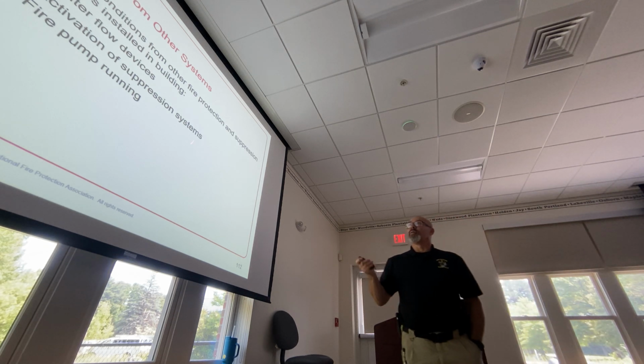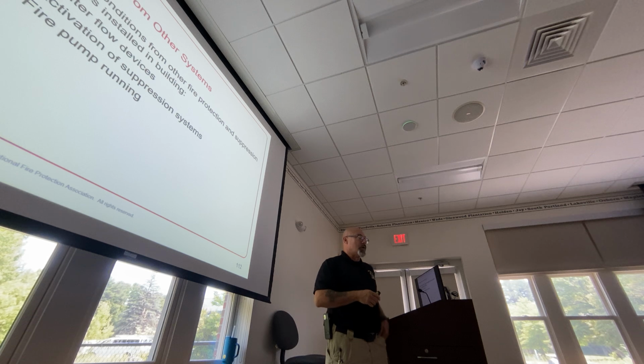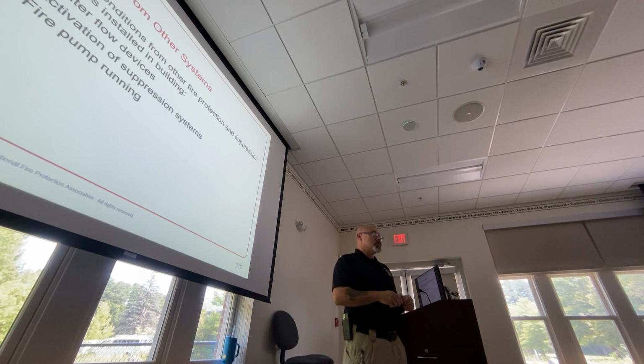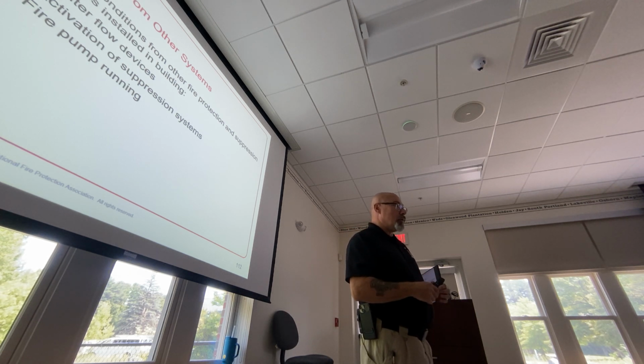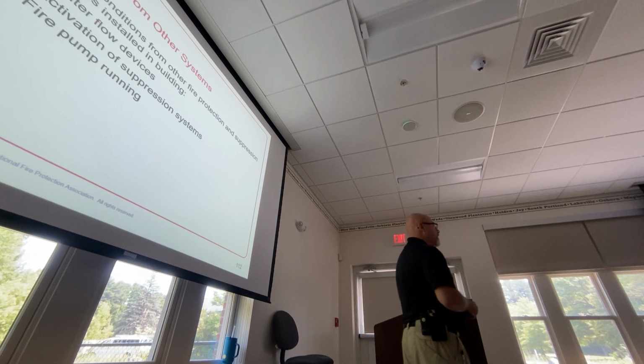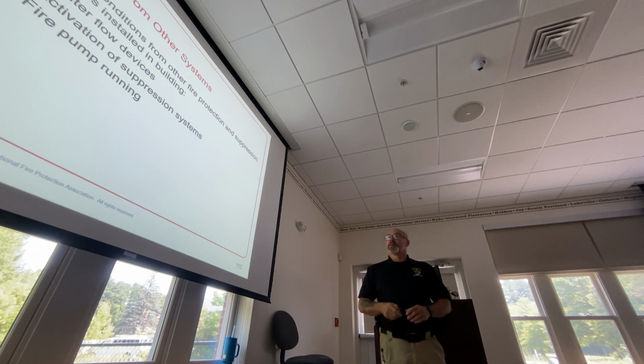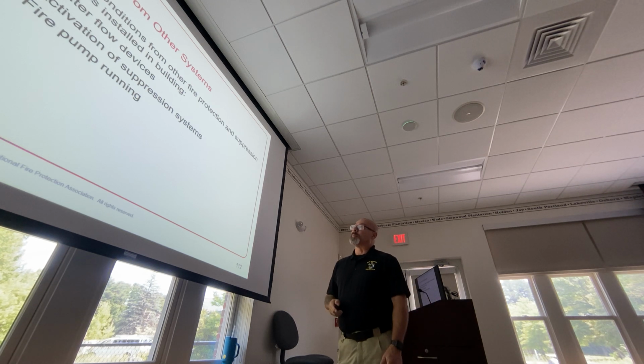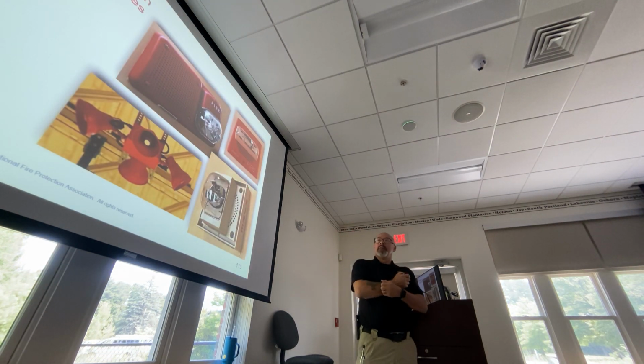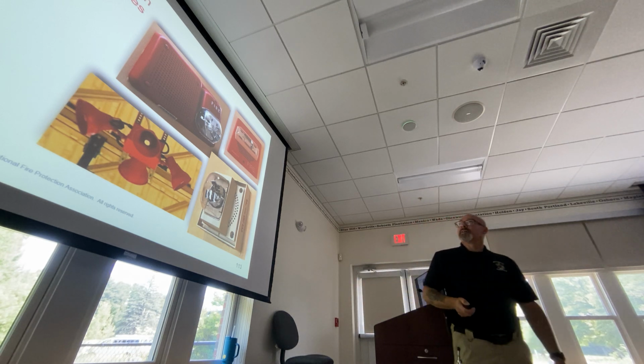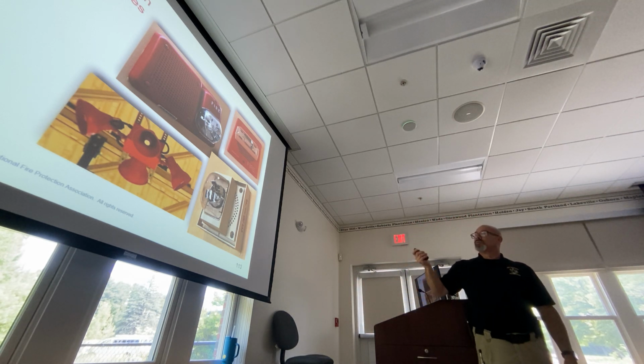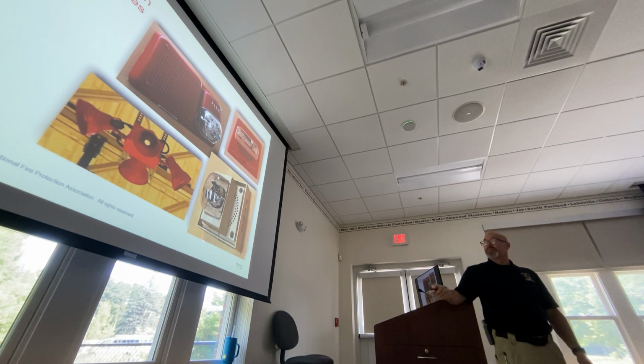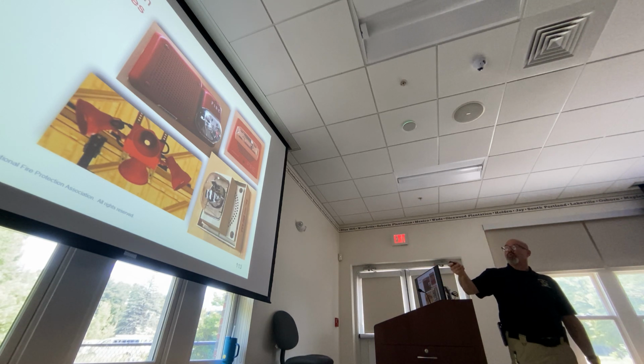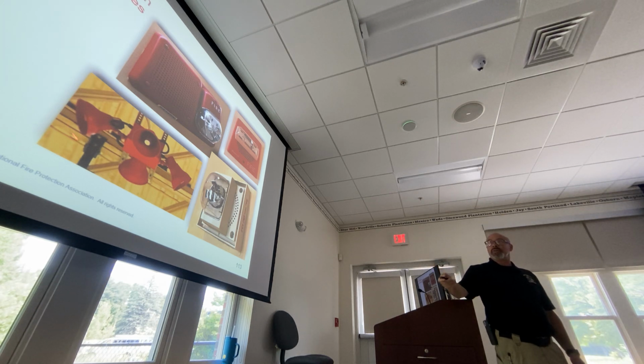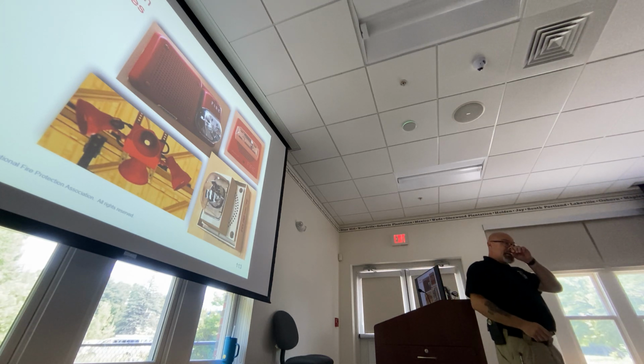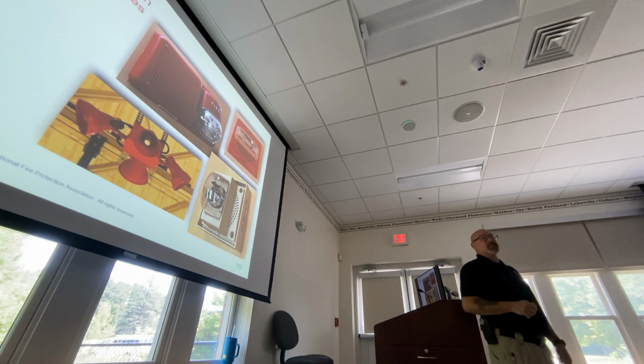They may not necessarily call the fire department. Those trouble alarms might notify locally, just to say, hey, there's something going on. We're in trouble here. Something's happening that shouldn't be happening. Or something's happening that's regularly scheduled to happen. Okay, notification appliances, they can be horn strobes like this, horn strobes like this, horn strobes like this. They could be just strobes only, or just horns only. Okay, it could also be screens.